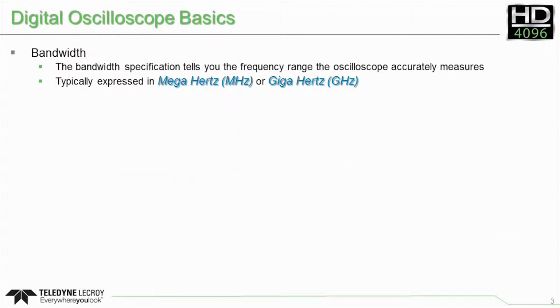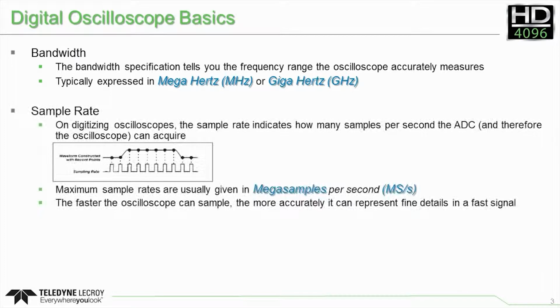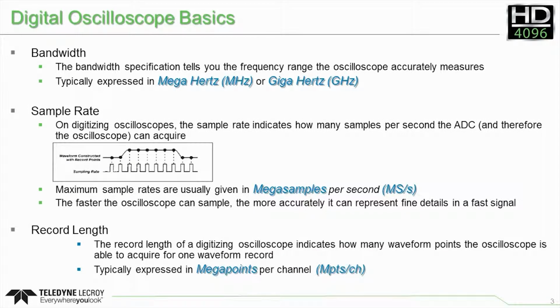Modern oscilloscopes have a few key banner specifications: bandwidth, sample rate, and record length. For years, oscilloscope manufacturers have developed innovative technology to improve all three of these key specifications, allowing engineers to capture higher frequency signals at faster rates and for longer periods of time. But for too long, one key banner specification has been overlooked: ADC Resolution.